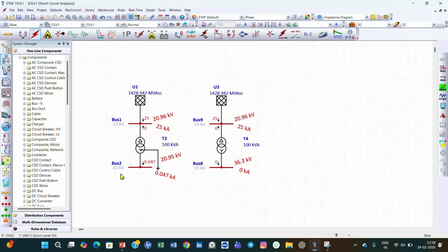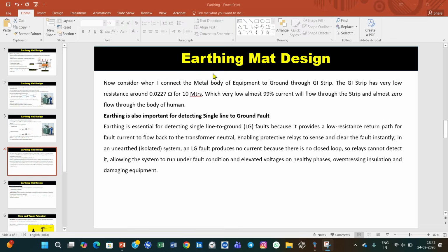Another problem is what is happening here: the voltage of the other phases is 20.95 kilovolts. This is a 33 kV bus. The voltage rise becomes 20.95 kilovolts, but here you can see the voltage has risen to 36.3 kilovolts. That is what I am saying, that in a single line ungrounded system, the voltage rises on the healthy phases and causes voltage stress. That is the thing which I am explaining here.